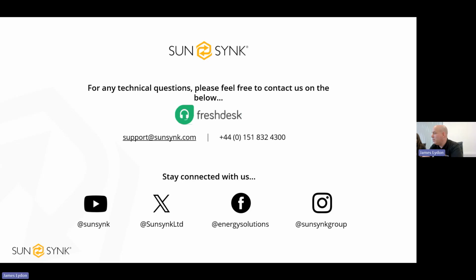What else have we got? For the generator import, is it possible to charge the battery with a generator without an ATS import if the end user manually started the generator? Yeah, absolutely. If the generator doesn't have that ATS signal, no issues with going out and manually starting that generator. Completely fine. But obviously with the ATS, our inverter will turn it on and off. Exactly the same rules apply for a manual generator: just make sure it's sized sufficiently to power the load and charge the batteries at the same time.